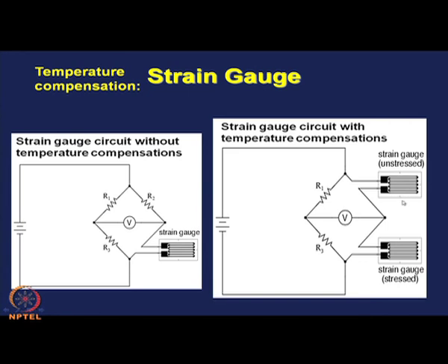Now, the effect of temperature will be the same in both the strain gauges. So, changes in resistance of the strain gauges by temperature alone will be the same in both gauges, but the strain gauge that is strained or stressed will have an additional change in resistance which comes from the strain.